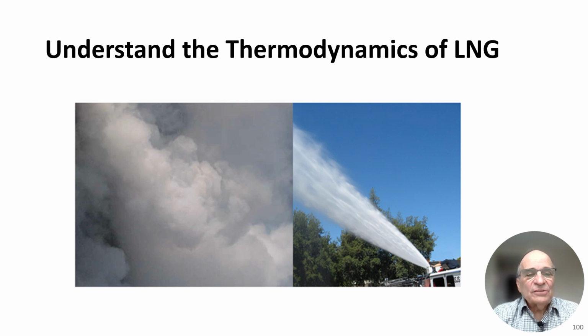Here's a thermodynamics question for you. Let's say I have steam rising from a location and I spray cold water onto that steam. Let's say I spray 100 gallons of cold water onto the steam, and then I collect the water that landed on the ground, and I find 110 gallons of water on the ground. Where did the extra 10 gallons come from? This cold water condensed the steam. And that's exactly what happens in a recondenser. If you have a recondenser in your plant, you are condensing superheated BOG using cold subcooled LNG.